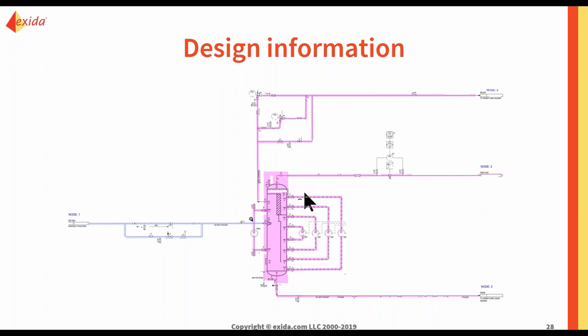So that was one of the paths that we took. We assumed that was the worst case, in a way that there would be overpressure, and because the feed gas was explosive and flammable, there might be possible loss of containment, so there might be a possible explosion. But if the design information shows that there's no way that the pressure coming in from the other units is going to breach the design limit of this particular vessel, then this particular scenario is actually not valid.